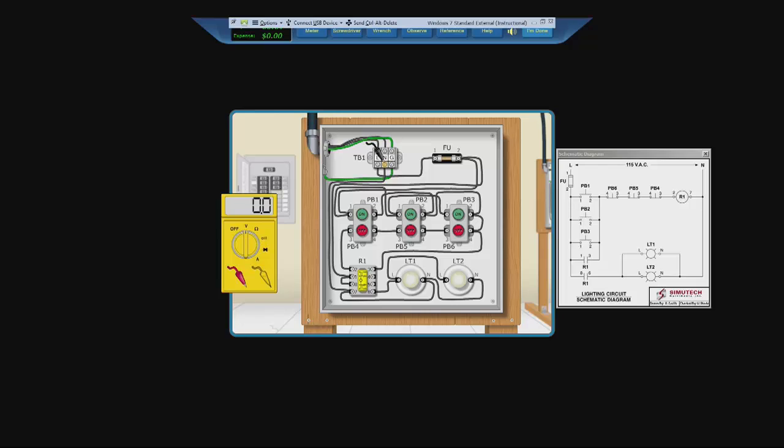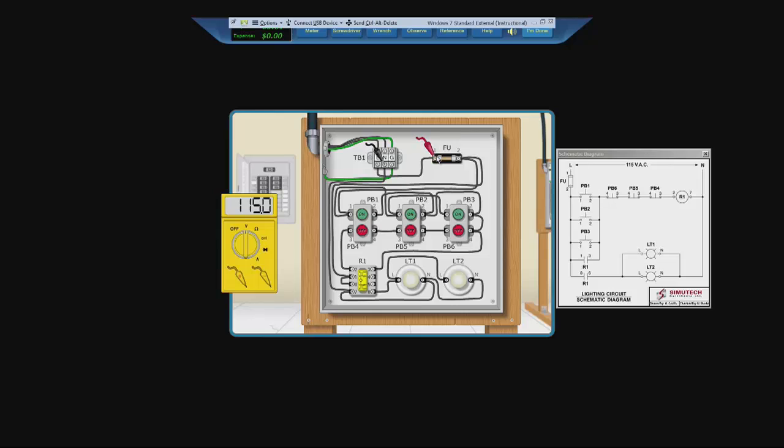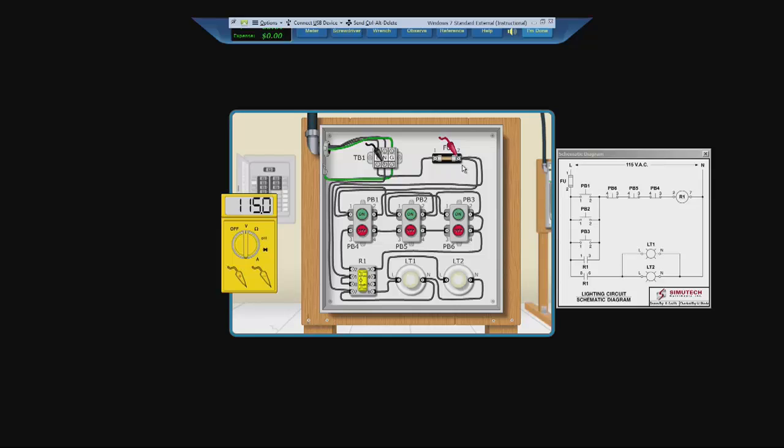So put your black lead on neutral, and your red lead on the fuse at point one. We have power flowing from terminal block one to the first part of the fuse. So now let us click over here. And we have power flowing through the fuse. This tells us that the fuse is fine, and something else is wrong with the circuit. Now obviously, multiple push buttons failing at the same time is not likely. In fact, very unlikely.